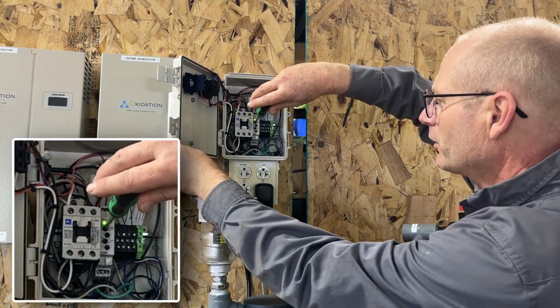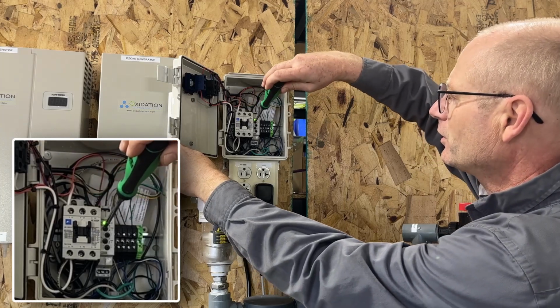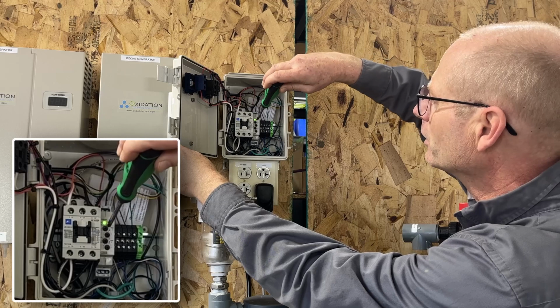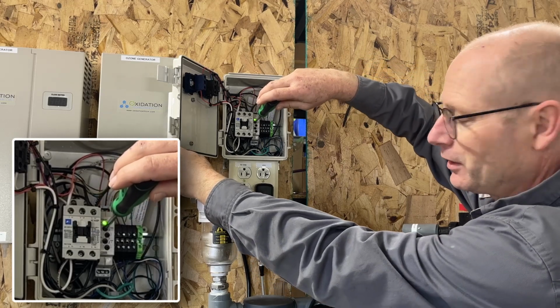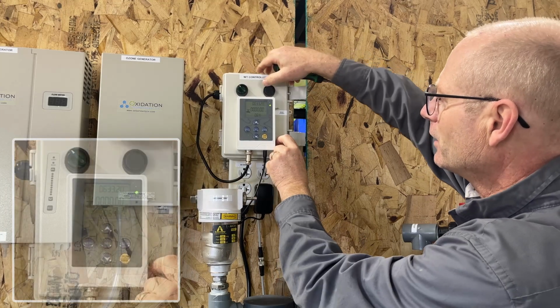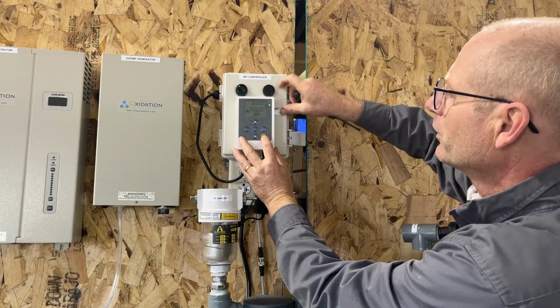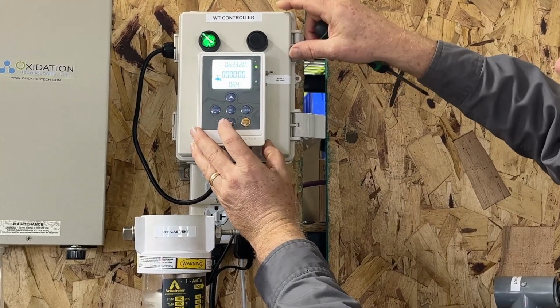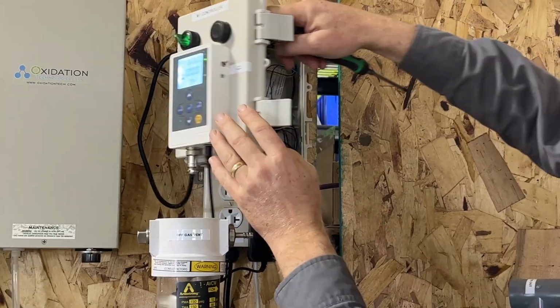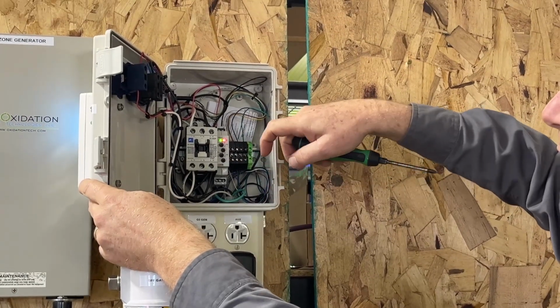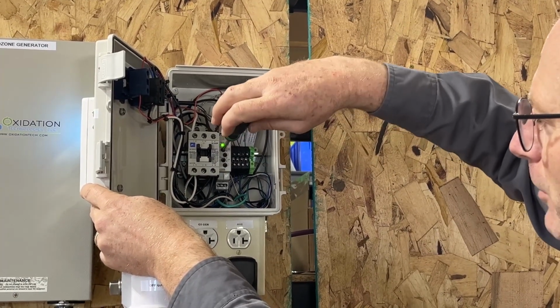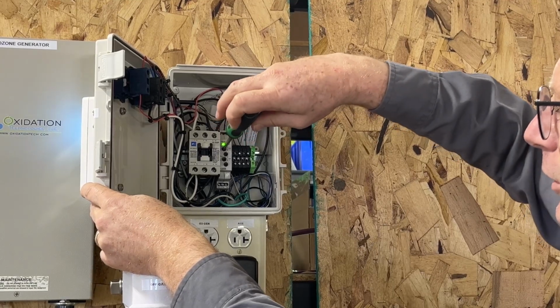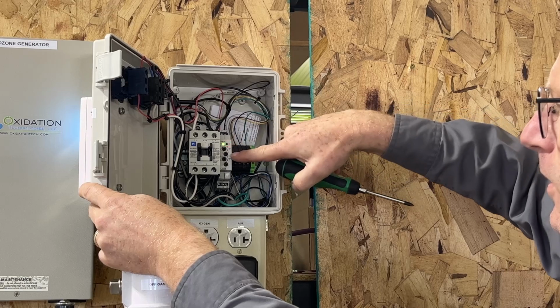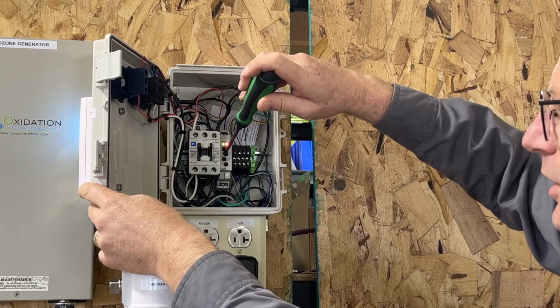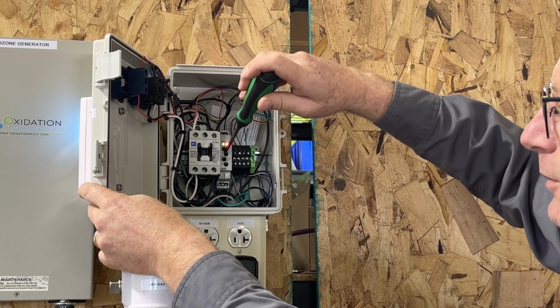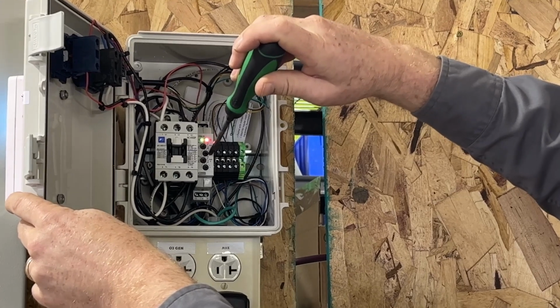Turn the top button, it's going to adjust from just a few seconds to hours. Right now I've got it set for about 1 minute so that it'll be on for a minute. When it's activated, you can press the run and it turns it on. As soon as that light's on, the contactor is on and your pump and ozone generator are on. I could turn this up higher so that it's on for a longer period of time, lower for a shorter period. The second one here, if you're set for 1 minute, will adjust the range from just a small portion of that minute all the way to one whole minute.